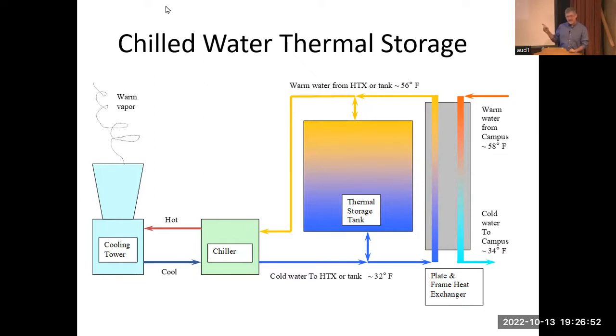This system takes heat out of a cold, chilled water system where we have a few million gallons of cold water, and it rejects it on the left-hand side through a cooling tower. I parked by the cooling tower originally that's on this campus, so I know if you go over on the back side of the main building, there are cooling towers. Now, after we talk, you should look at that cooling tower in a different way. That device throws away perfectly good energy. How could we recapture that energy? Well, we're going to build a system that's slightly similar to this, but now it doesn't waste the energy that we currently do. And it's not to take any shots at the people who designed the system, but it's to say we can do better today than we did decades ago when we built it.